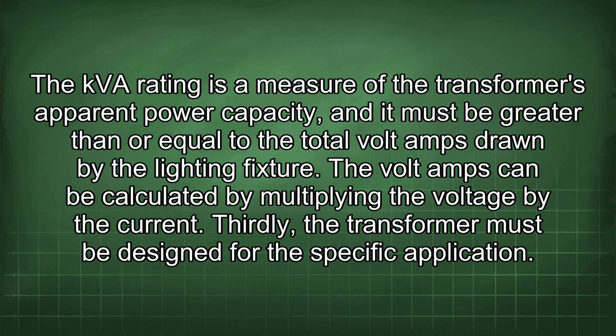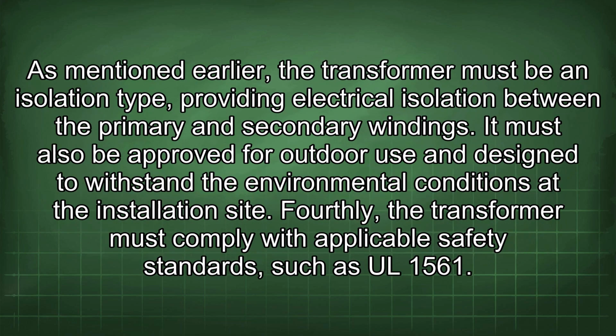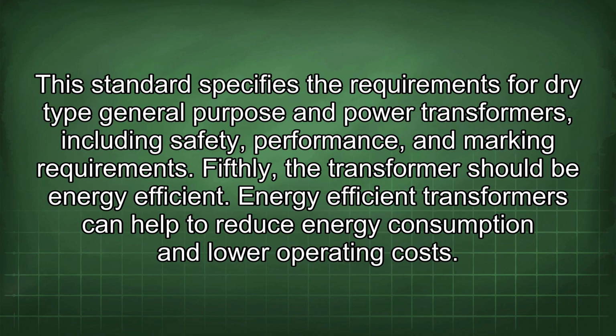Thirdly, the transformer must be designed for the specific application. As mentioned earlier, the transformer must be an isolation type, providing electrical isolation between the primary and secondary windings. It must also be approved for outdoor use and designed to withstand the environmental conditions at the installation site. Fourthly, the transformer must comply with applicable safety standards such as UL 1561. This standard specifies the requirements for dry-type general-purpose and power transformers, including safety, performance, and marking requirements.